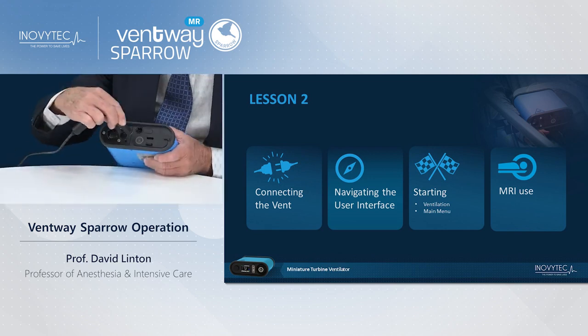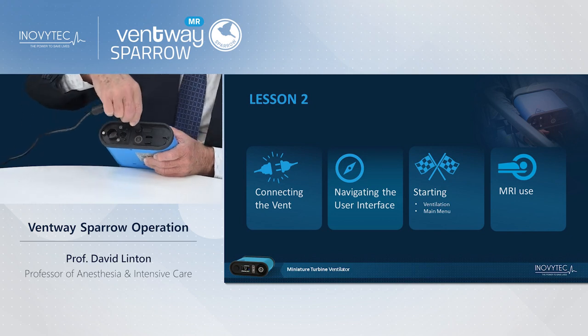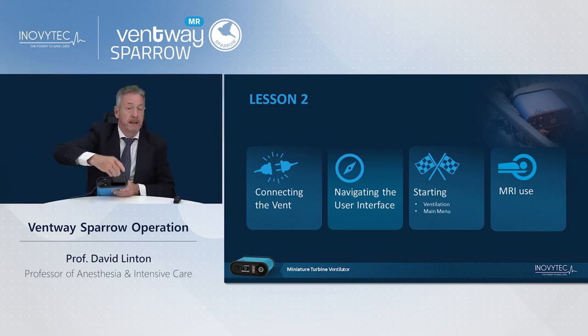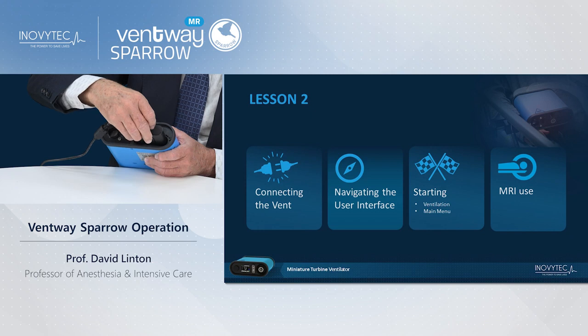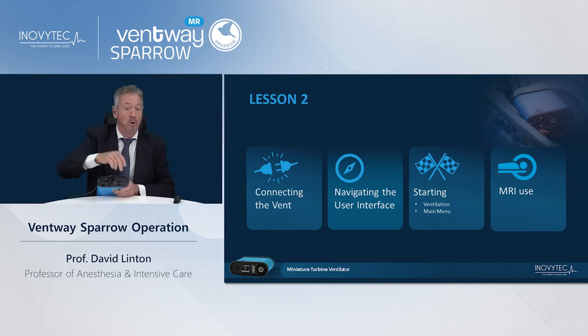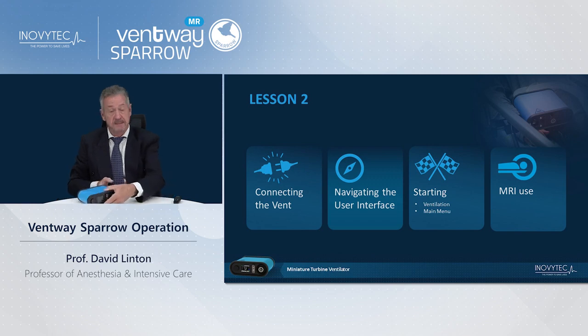The ventilator has a place to plug in the electricity at the back, and a battery pack which is either fully charged, giving you 4 hours, or will be charged by the electrical input. Secondly, you have to provide an oxygen supply to the ventilator. You do not need a pressure source for air for this ventilator because it has a turbine.